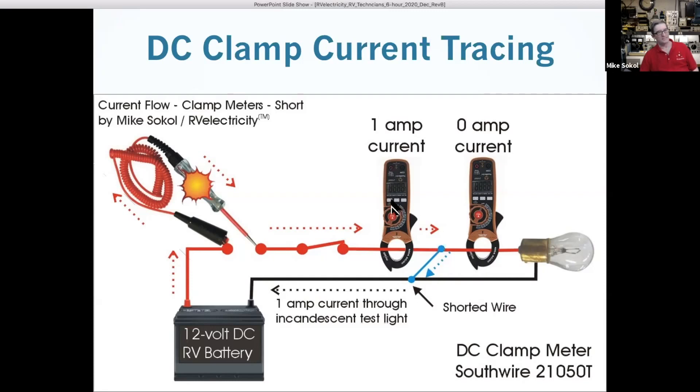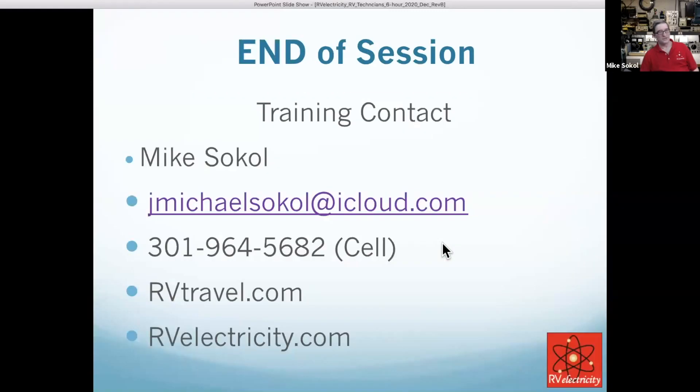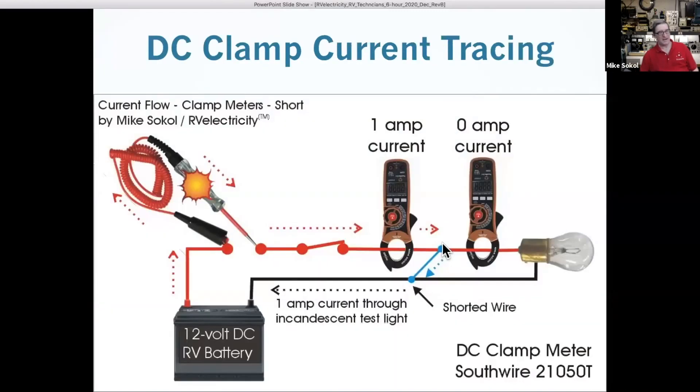You put this in here, turn this on, now you have an ampere or so flowing through here. Take your clamp meter and just start clamping around the wire. You clamp it here and you got an ampere, clamp it here and you got an ampere. When you clamp it over here, there's no current flow, so you know somewhere between here and here is the short. Then you can visually inspect that and start to find where it is.